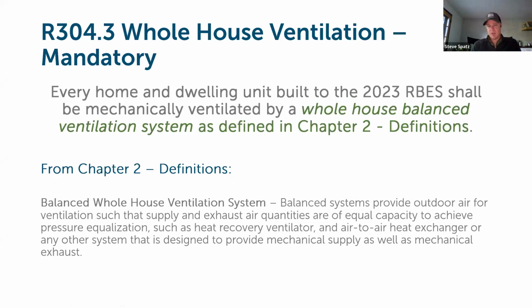Big change for the 2024 RBES is that up until now, exhaust-only ventilation was allowed in the code, meaning that you could provide the minimum requirements for mechanical ventilation, whole house ventilation in RBES, by using bath fans that were controlled to run automatically throughout the day. So exhaust-only systems have essentially been the baseline allowable to this point. The change for 2024 as of July 1st is that every home built to meet the new updated code will need to have a whole house balanced ventilation system installed. So exhaust only is no longer going to be allowed. We're going to be looking at balanced heat recovery ventilation equipment as the mandatory standard moving forward.